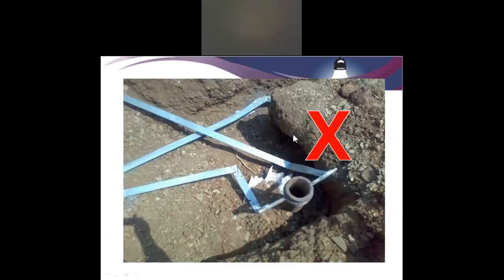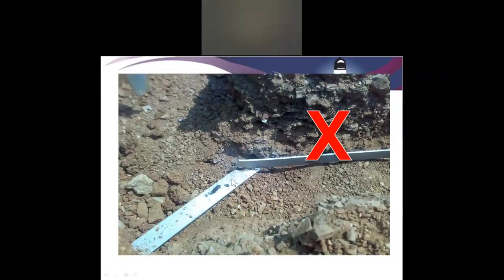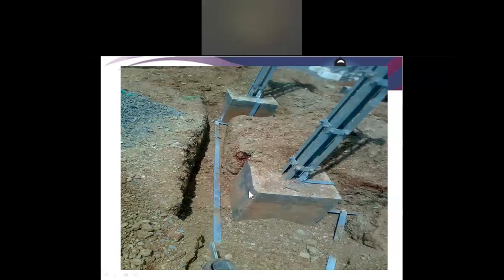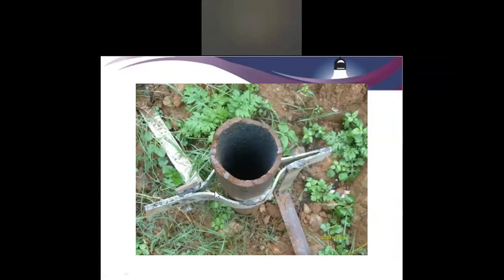These are the wrong practices to carry out - bending and crossing are wrong practices. You know the common sense logic behind this is always wrong, because whenever a fault happens, we should make it like a highway so that it immediately penetrates and sinks into the earth. These are the things we carry out in the field. This is a wrong one - it should not have a gap like this. It is not welded, so these are rejected ones.